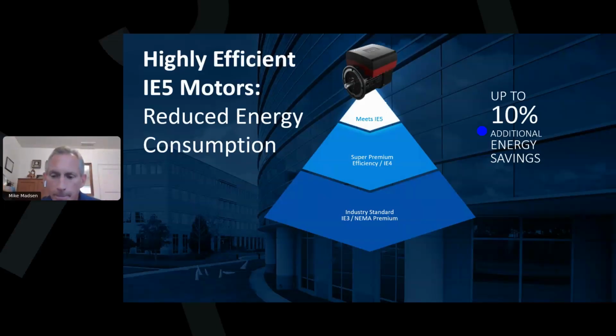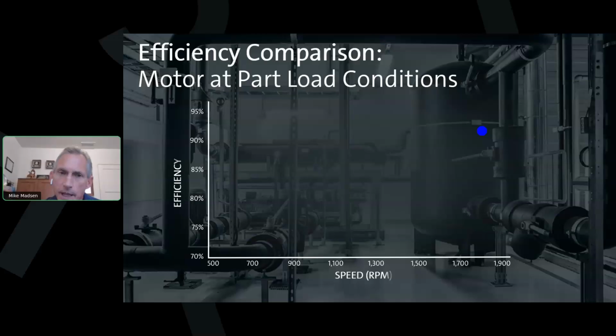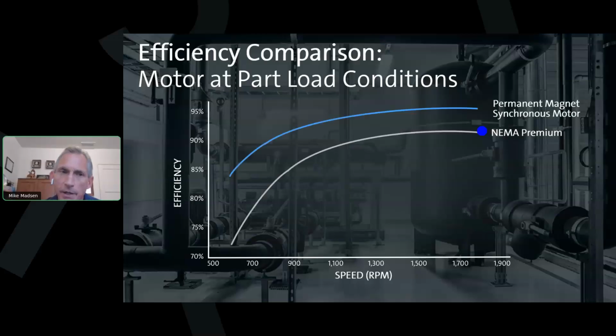Hey, Mike, are these IE5s, are these EC motors? They are. They're ECM motors, permanent magnet motors. Okay. And for my product, I actually have this motor available through 30 horsepower. So depending on the manufacturer, they have different things available. The story is actually much more interesting than just saving 7 to 10% energy.